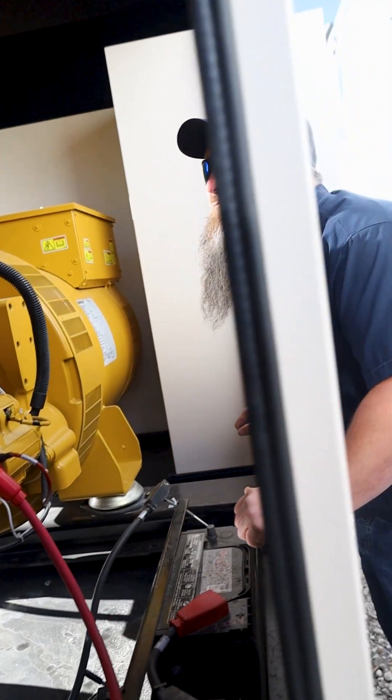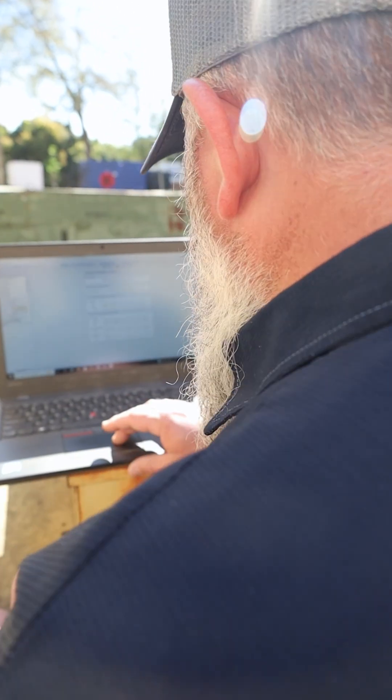If you see any of these issues occur, it's best to call an expert technician to assess the generator. Common causes of overheating include blocked airflow, low coolant levels, coolant system problems, or overloading.